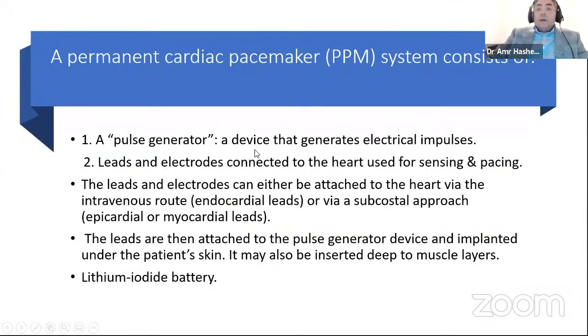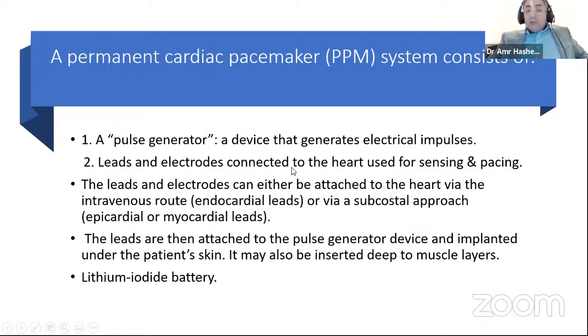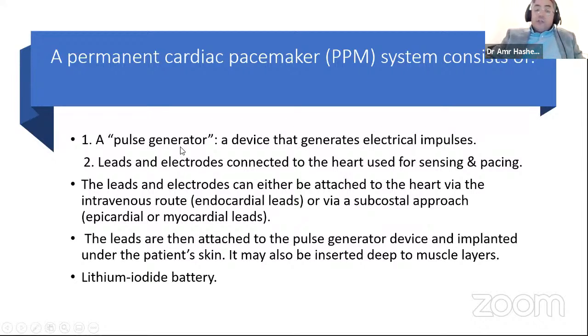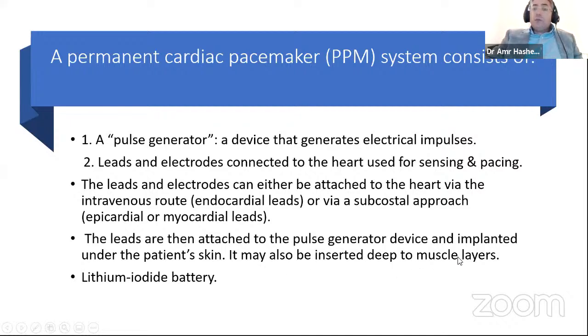A permanent cardiac pacemaker consists of a pulse generator — a device generating electrical impulses — and leads and electrodes connected to the heart for sensing and pacing. Leads can be endocardial (via intravenous route) or epicardial/myocardial (via subcostal approach), with the generator placed in the chest wall or abdominal wall. Leads are attached to the pulse generator and implanted under the patient's skin, sometimes deep to muscle layers, powered by a lithium iodide battery.